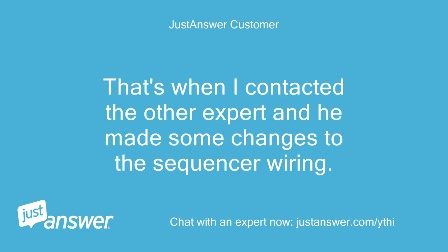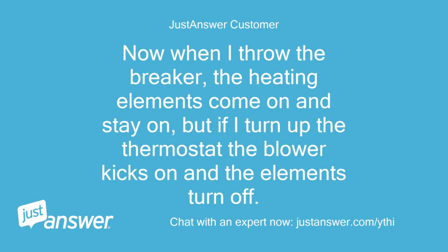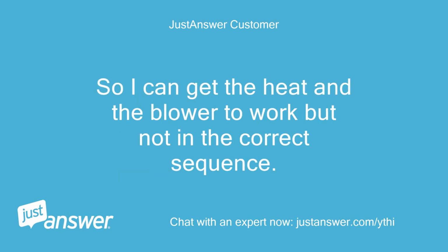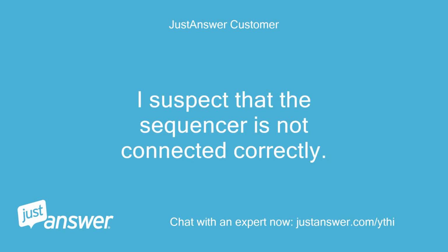That's when I contacted the other expert and he made some changes to the sequencer wiring. Now when I throw the breaker, the heating elements come on and stay on, but if I turn up the thermostat the blower kicks on and the elements turn off. So I can get the heat and the blower to work but not in the correct sequence. I suspect that the sequencer is not connected correctly.